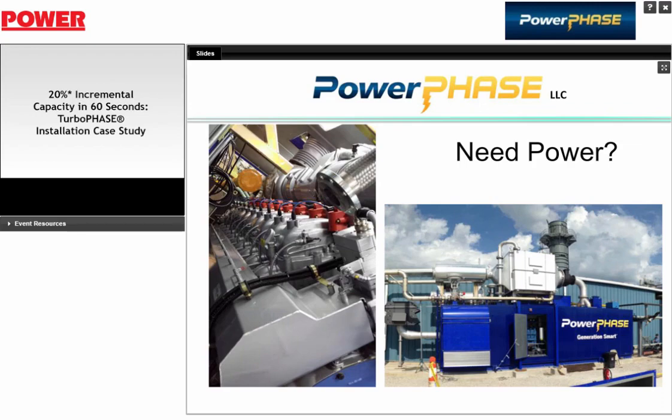All right. Another question about cooling water. How much cooling water is required per unit? The system is set up for 600 gallons per minute. It's a closed-loop system. Maybe you can't tell from the picture, but there's no radiator in the system. So water comes in a 6-inch pipe, 600 gallons per minute.